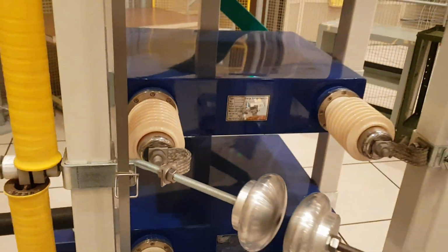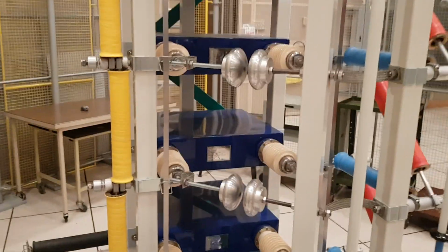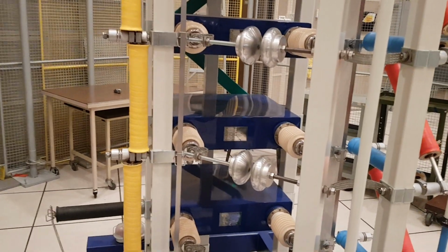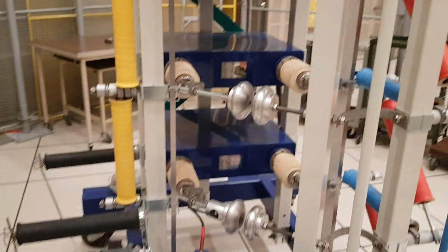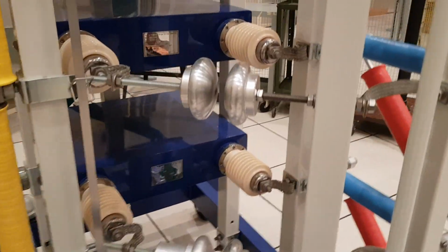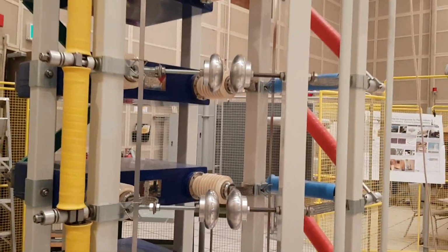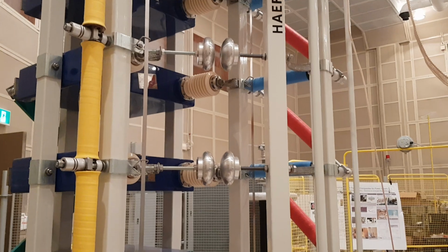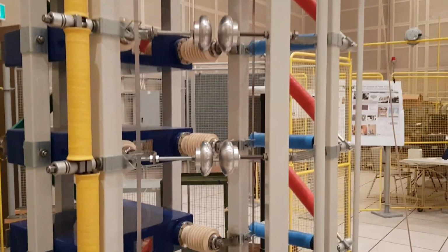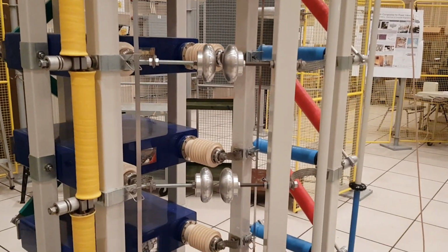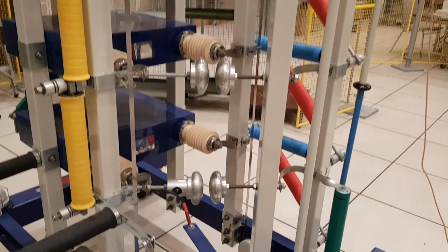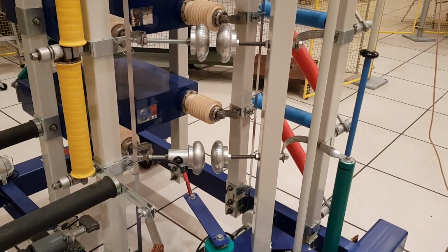Now, these capacitors, as I mentioned, we charge them in parallel and discharge them in series. And how is this done? Using the sphere gaps that we saw here. As you can see here, in every stage there is a sphere gap. And these sphere gaps are normally open circuit, but then at a certain time they short circuit. This basically happens when the capacitors start to discharge and their voltages will be adding up.